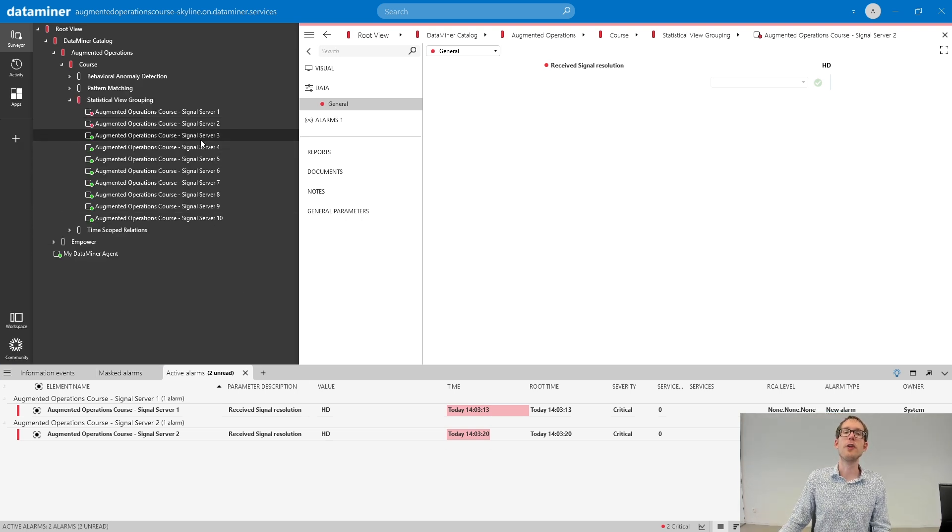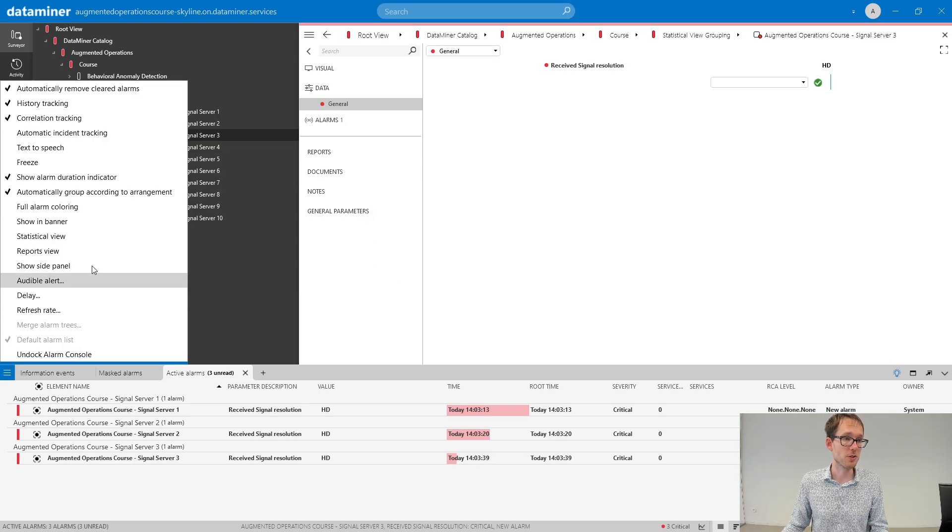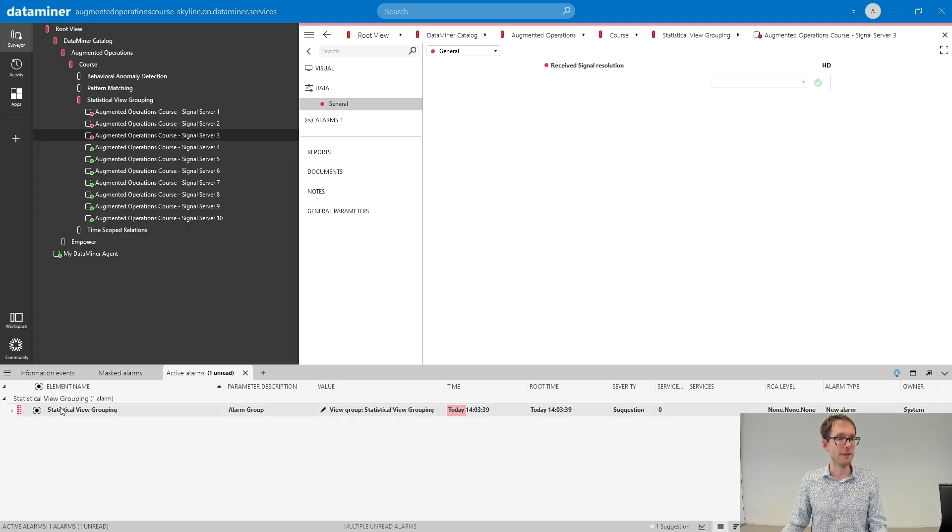Let's add an alarm on a third device. If I do that, then 30% of the devices under this view are in alarm. The threshold is set to 25%. So we should be able to group this. And indeed, you see the alarm grouping grouped those three alarms based on the fact that they belong to the same view called statistical view grouping. And that's indeed the name of this view.